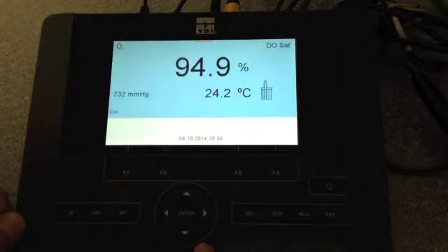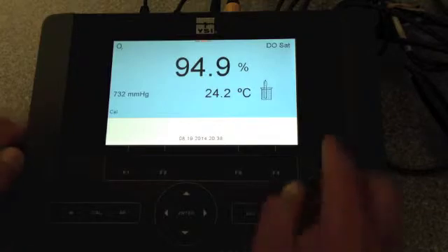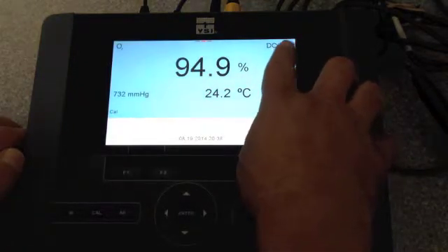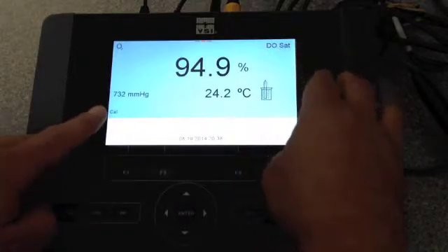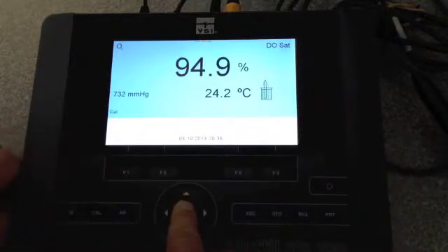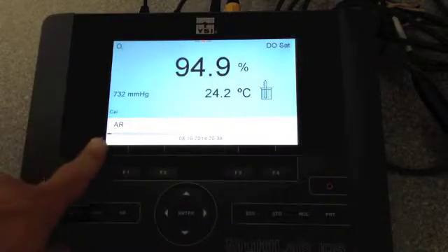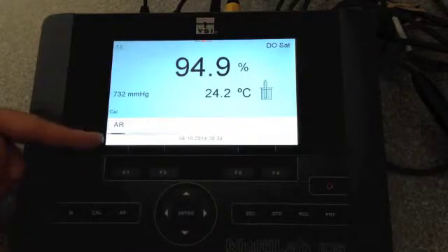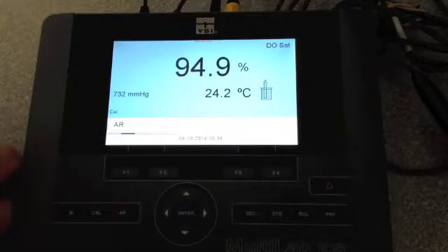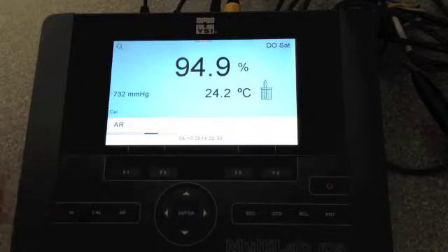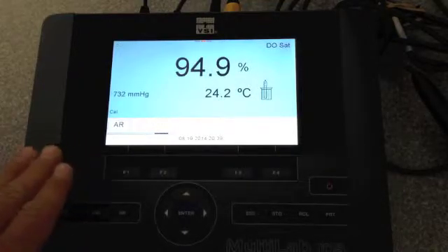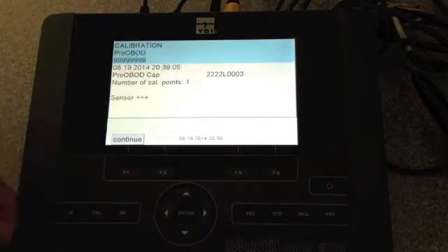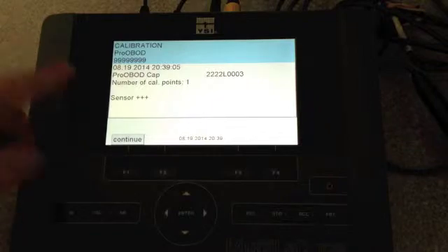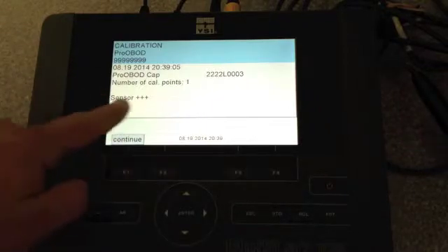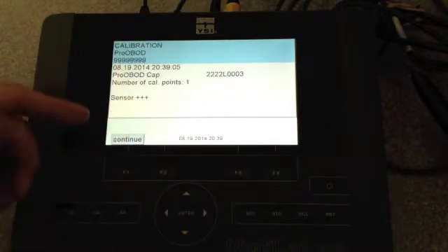I'm going to hit the calibrate button, and it tells you the modes we're in, and we're going to hit enter after we hit the cal. Once we hit enter, it has an auto read function, and you can take a look down below that it's in the process of calibrating itself. This same procedure will be used for pH and the other ISEs as well. After the DO is done, it lets you know that the calibration was successful. It does have some indicator arrows that let you know about the condition of your sensor.